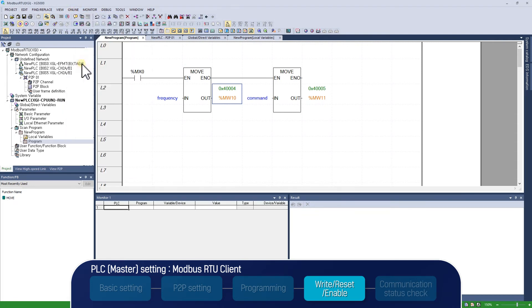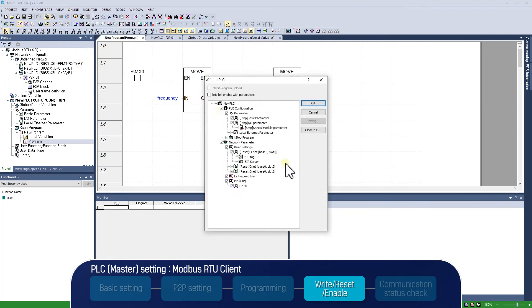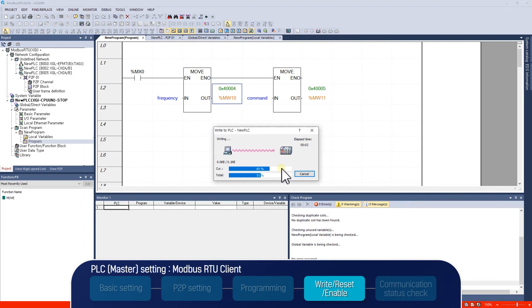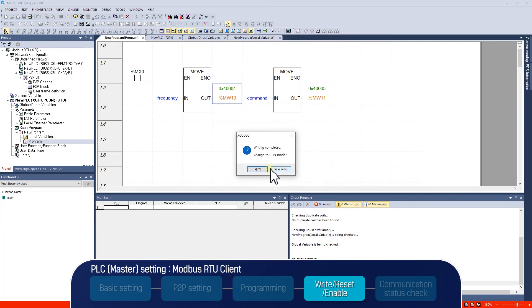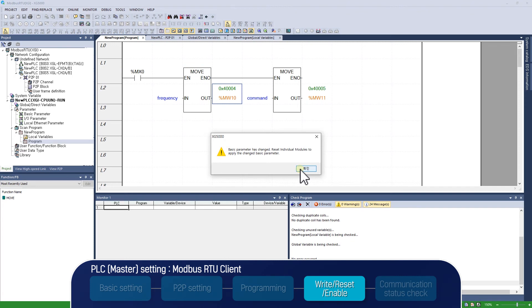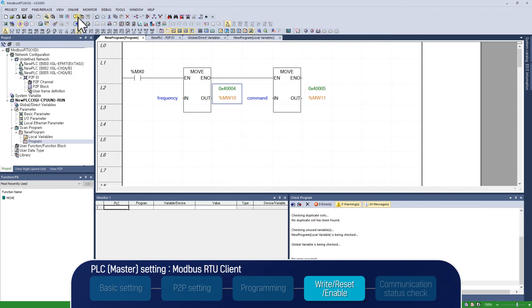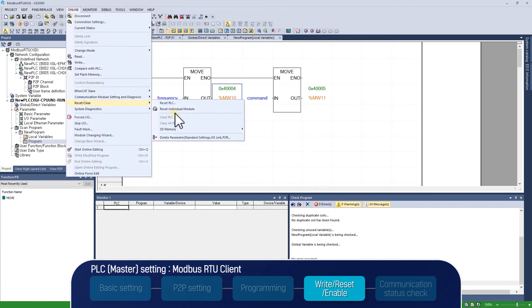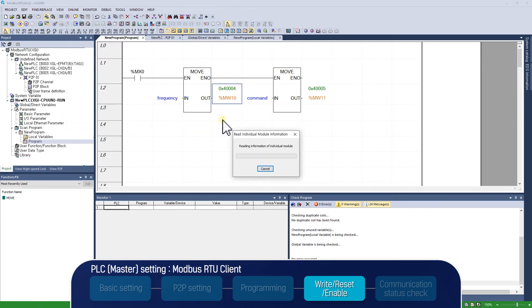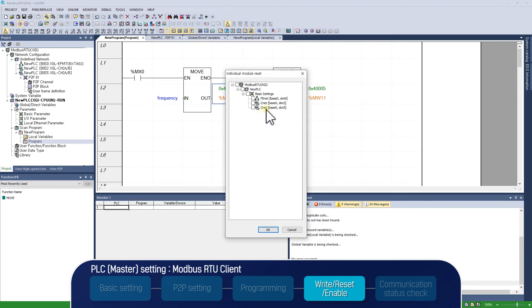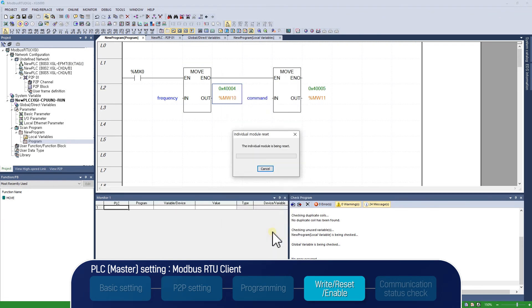Select Online, Write. Make sure Network Parameter, Basic Settings, and P2P is selected. After downloading, CNET Communication Module is to be reset to update the parameters. To apply the updated Communication Module setting, you are supposed to click Reset PLC or Reset Individual Module. Reset Individual Module will reset the selected Communication Module when PLC runs.